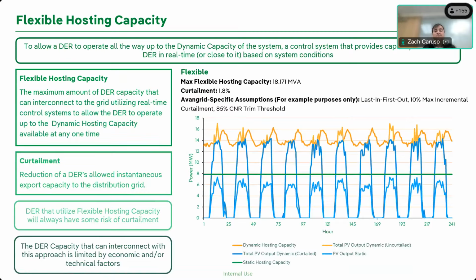And that really gets us to the final point of this idea of flexible hosting capacity, right? Which is, now I can allow, if I have some sort of control system in place that is dynamically monitoring that constraint, assuming it's a substation thermal constraint, it's monitoring the current flow through the transformer bank, and it is dynamically feeding that information back about how much capacity is available to the flexible DER on the circuit, to allow their output to be curtailed if needed.